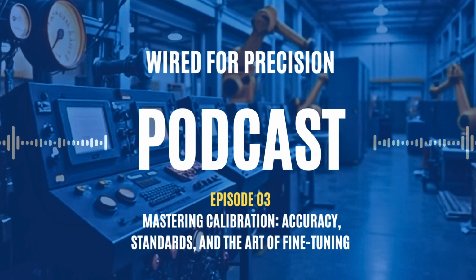Here are key best practices you should follow during field calibration. 1. Establish a baseline, as-found reading. Always begin by recording the instrument's readings before any adjustments. This as-found data is critical for traceability and analysis.